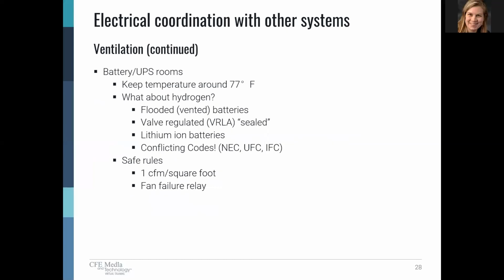Battery rooms, UPS rooms. Here's where you want to keep the temperature even lower. There are a lot of different types of battery technology that have been used over the years. Flooded, vented batteries were the old technology. Most often, sealed or valve regulated batteries are used. Lithium-ion batteries are gaining ground. Their prices are coming down.